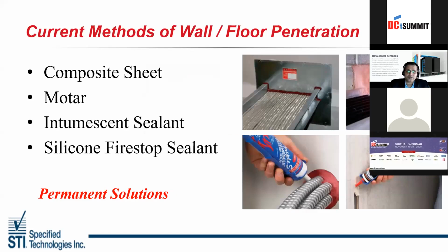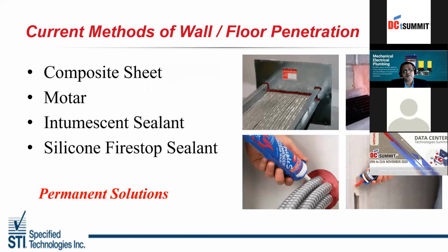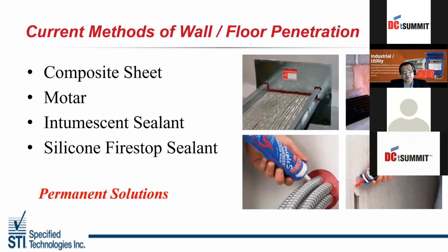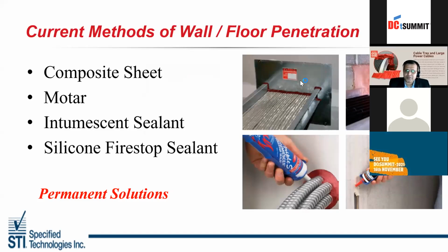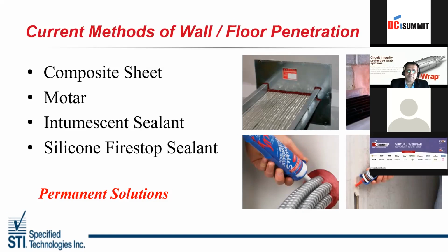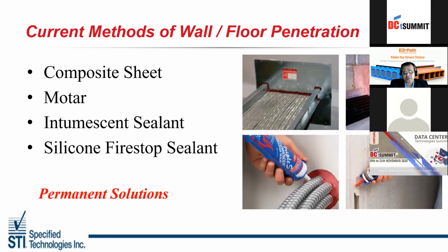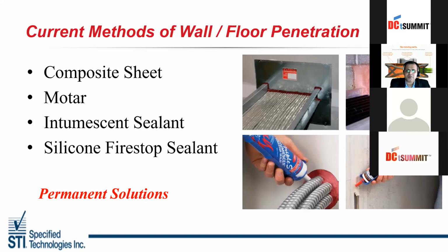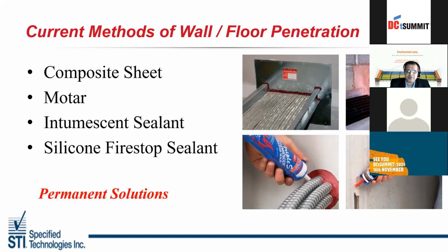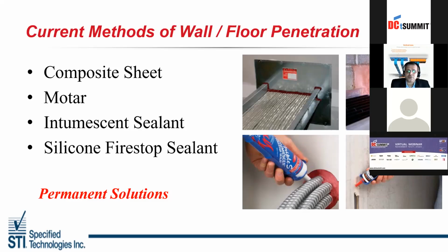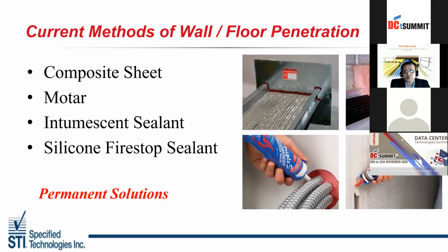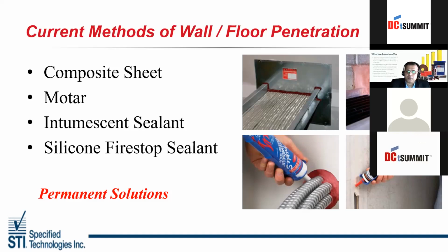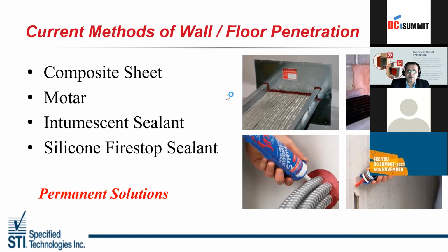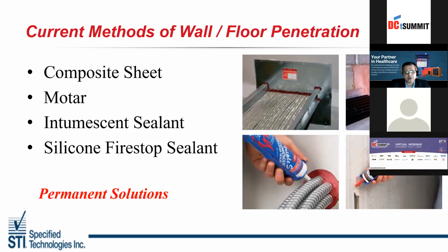These are the permanent solutions. You have composite sheet, you have mortar, you have intumescent sealants, and you have silicone fire stop sealants. Composite sheets are thin 2.5 mm GI composite sheets, which are up to 4 hours fire rating. These sheets are used when you have multiple cable trays, and you foresee that cables can be changed or additional core cutting has to be done. This is a very thin composite sheet, which can be easily cut with an industrial scissor, the 2.5 mm thick sheet. Mortar is a fixed solution wherein once installed, if you need to do additions or changes, it has to be broken, damaged and then redone. Intumescent sealant, I've already explained. And silicone sealants are used wherein you need a W rating, water leakage rating.